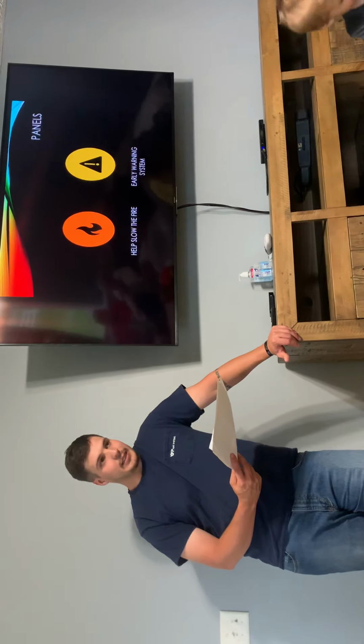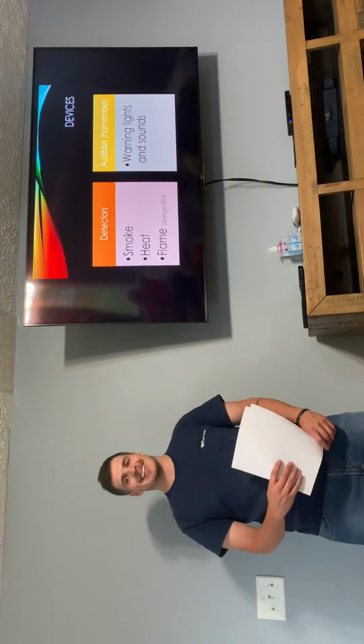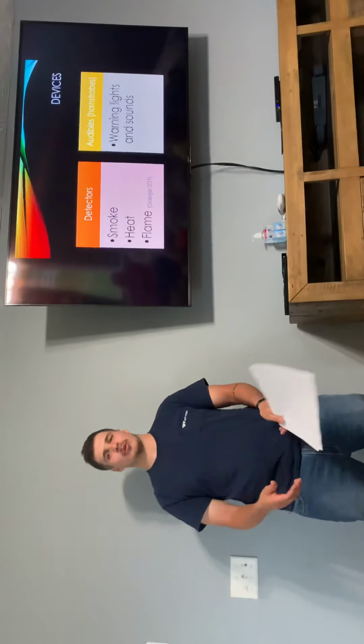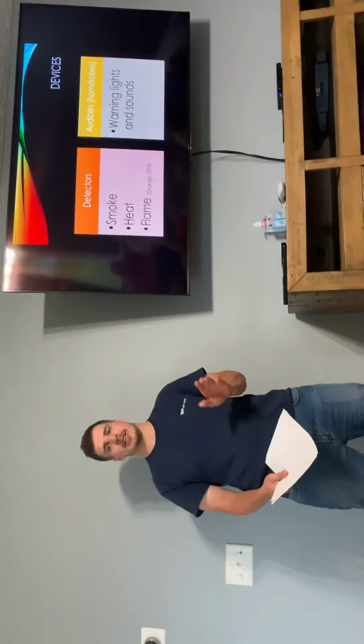Panels, the devices: detectors, smoke, heat, flame, and warning lights and sounds. You got many different types of smoke detectors. You got photo smokes, and also smokes that are called ion smokes. The photo smokes detect smoke with a light sensor, a laser, and when the smoke comes in and breaks the laser apart, it triggers the device and tells the panel to call the fire department.